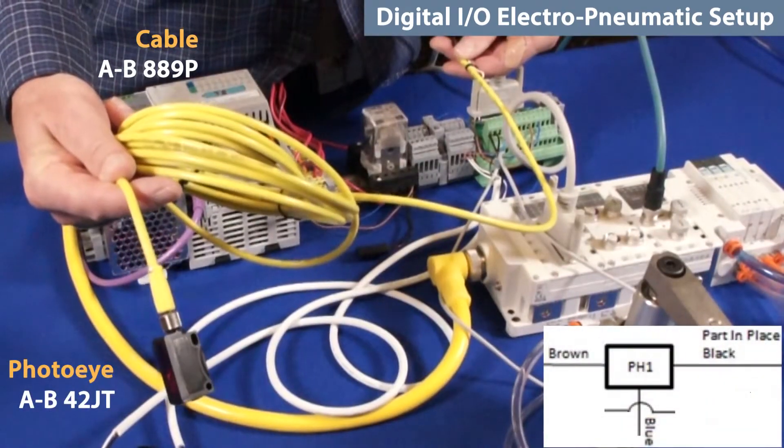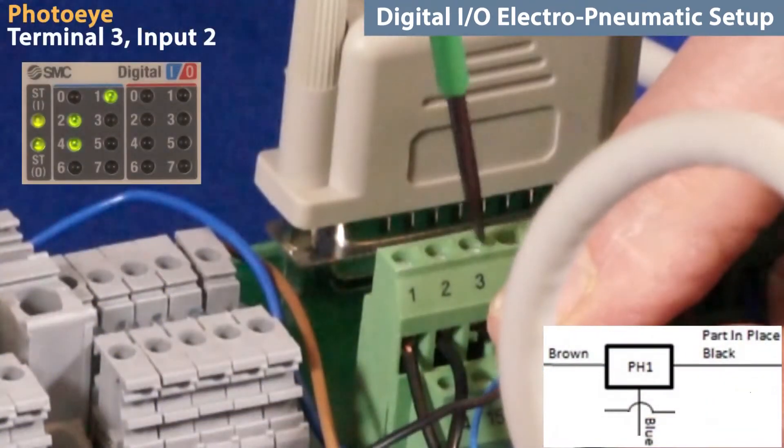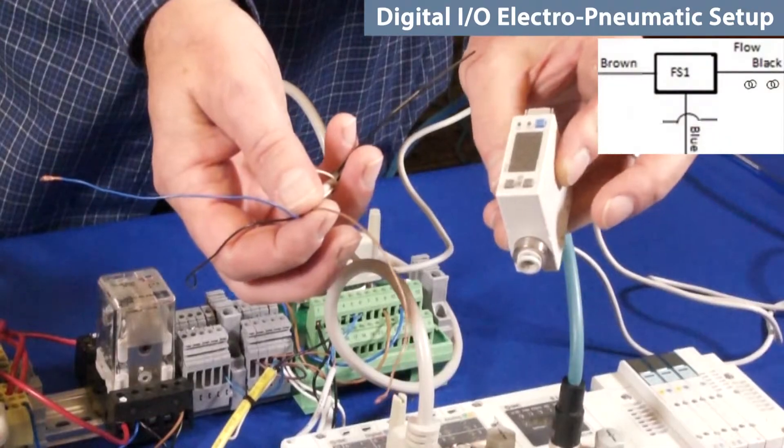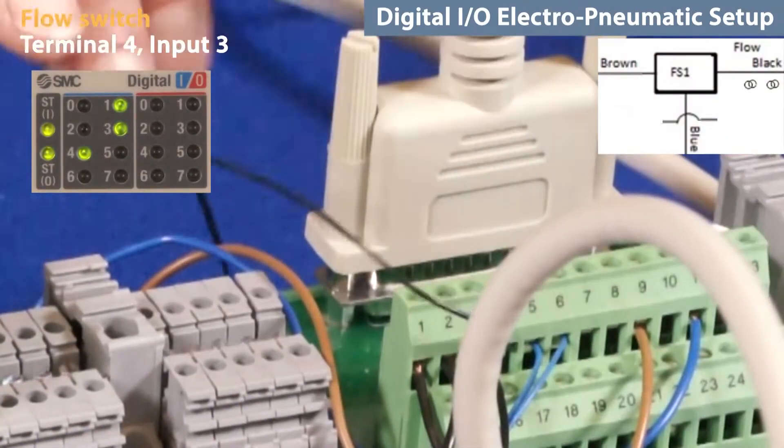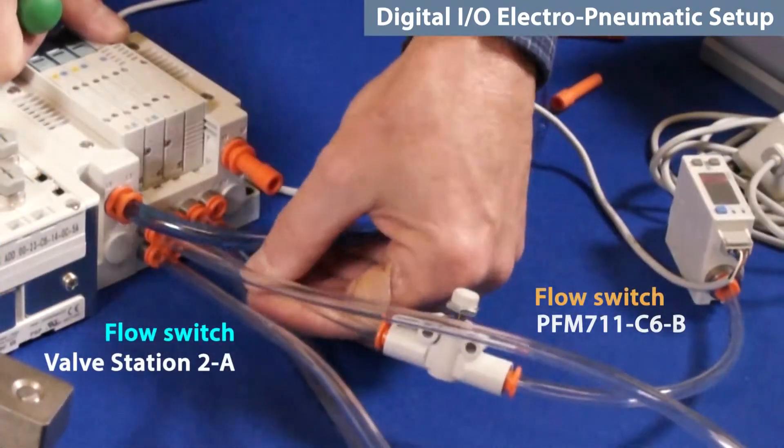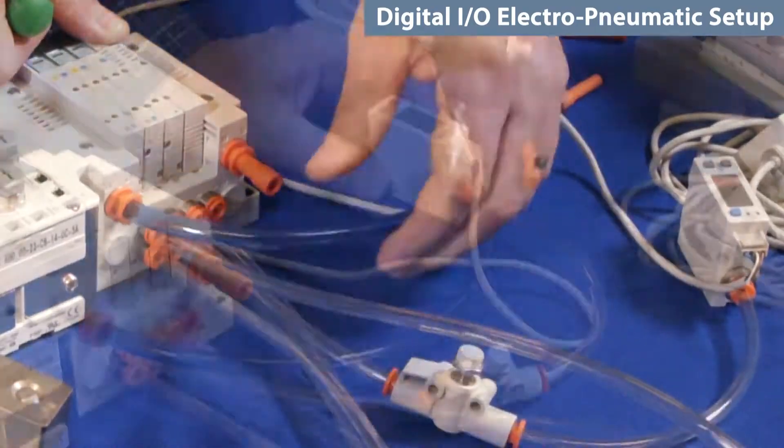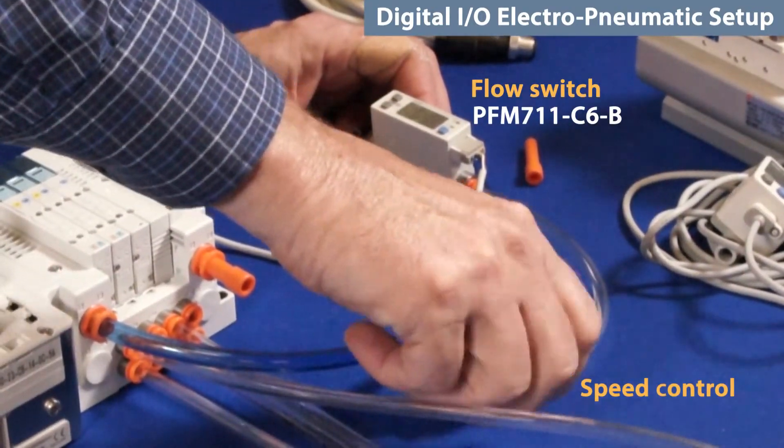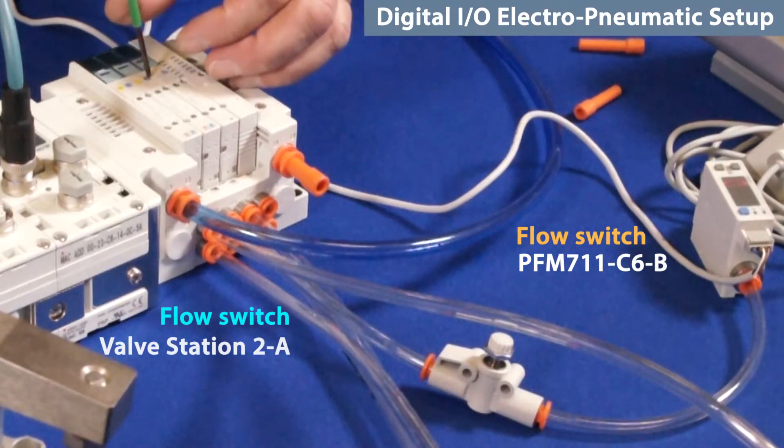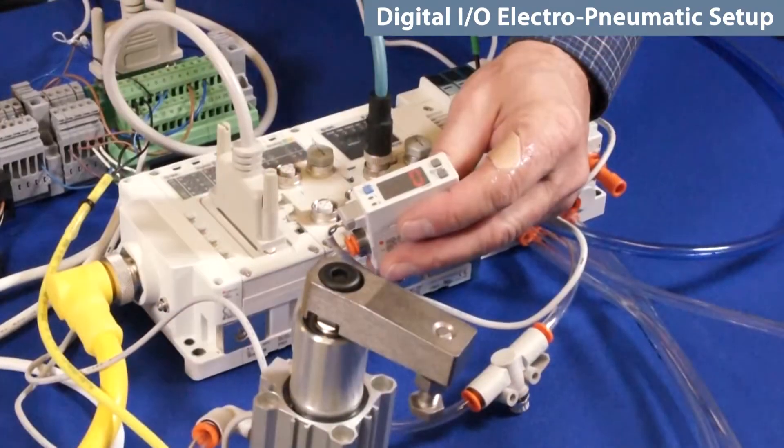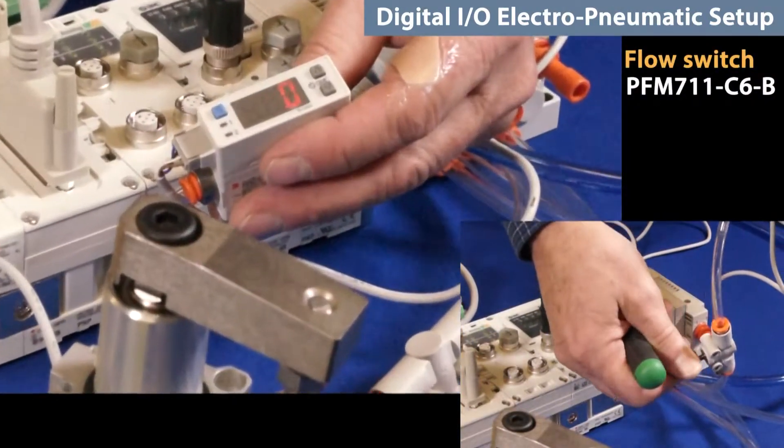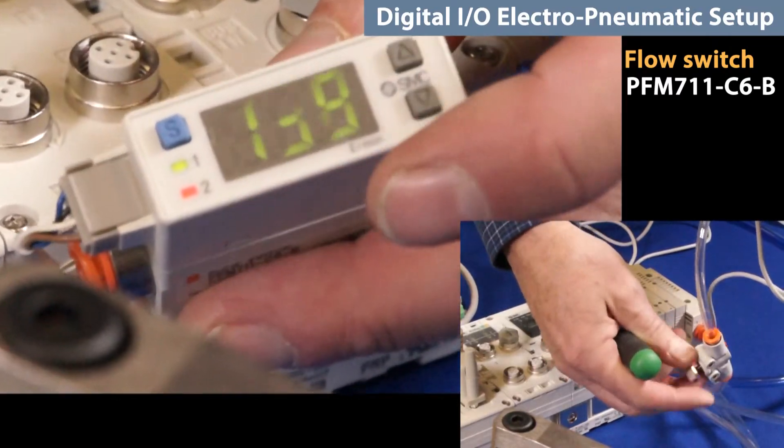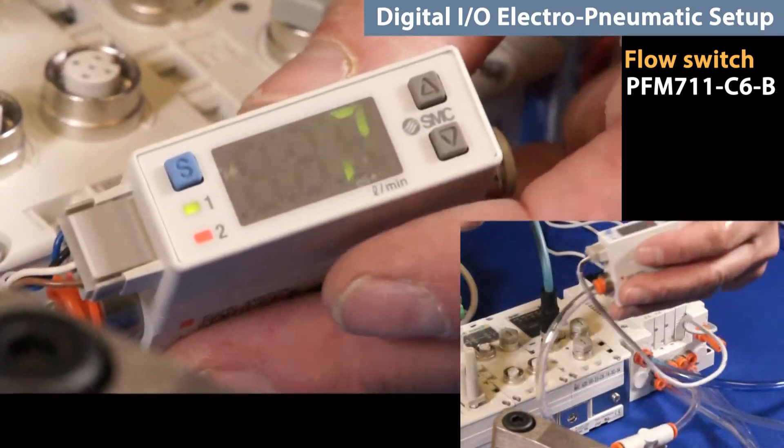Wire the photo-eye components and again verify with the module lights. Now, wire the flow switch before connecting its tubing. Connect the flow switch to the valve output that we want to monitor. Set the flow switch output to 60 liters per minute. With source air on, manually override the valve station and gradually open up the speed control. The output LED on the flow switch should turn on at 60 liters per minute.